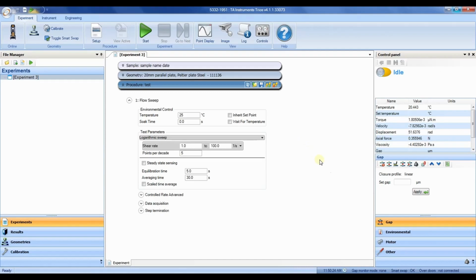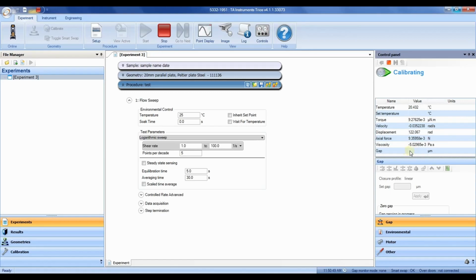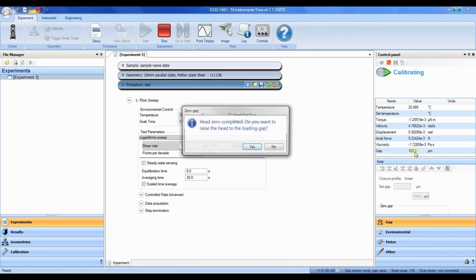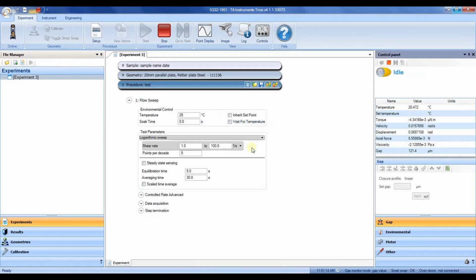To load your sample, first we need to zero the gap. Now the rheometer moves the upper shaft until the gap between both of them is 0. The gap value changes once both the plates are in contact. Once the head zero is completed, you see this pop up and hit OK. Now we move plates to loading gap.